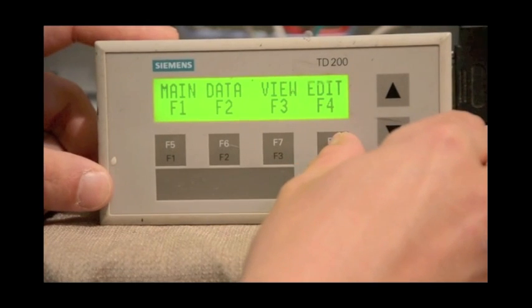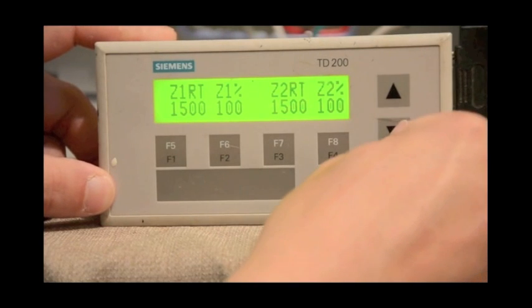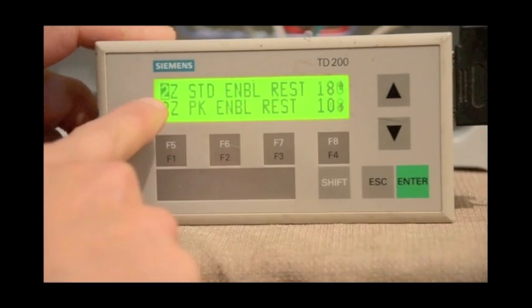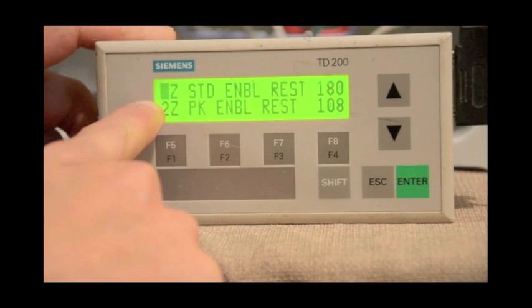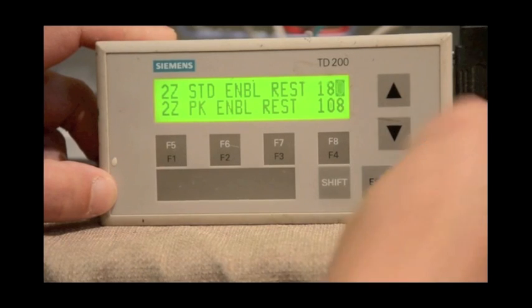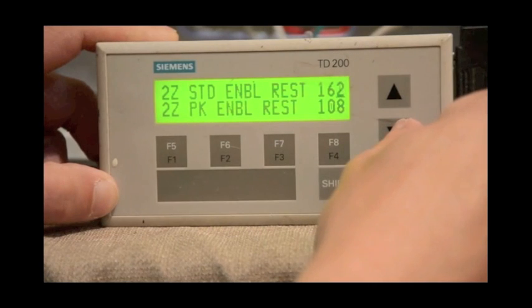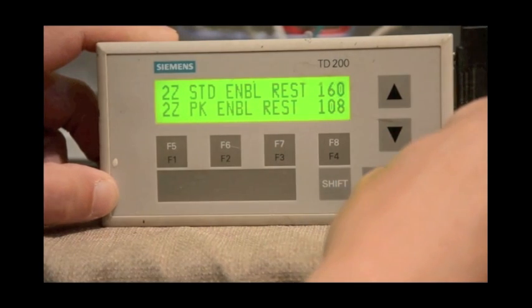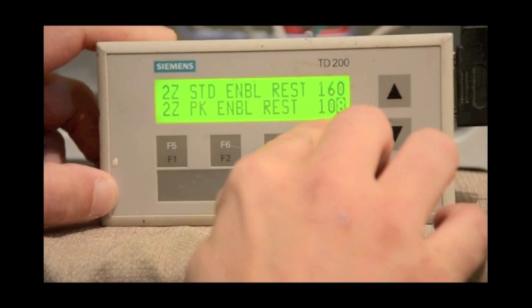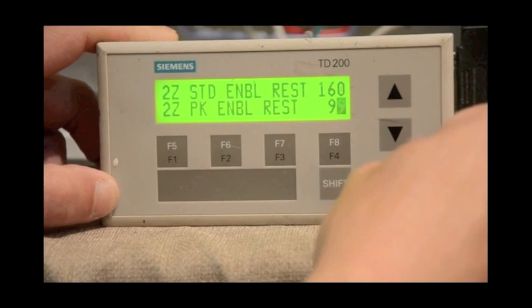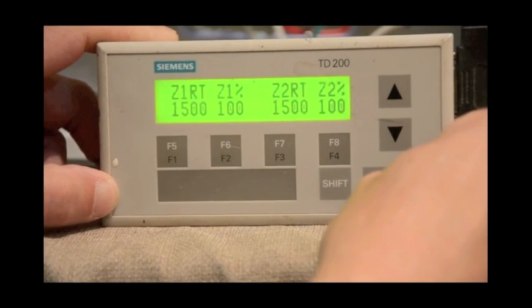Adjusting the rest times is also done using the F4 edit button. Once you've hit F4, use your down arrows to scroll down to the number of zones that you have in your system. In our case, we're playing with a 2 zone. Once the cursor is flashing on the correct line, press enter to move to the adjustable time. Using your down or up arrow key, adjust the rest time to your desired value. You can also press enter to move down to the peak rest time. These are independently adjustable. The same thing, go ahead and adjust your peak rest. Hit enter, which will take you back to the beginning of that F4 screen. You can come back to your zones to confirm that the data is now reset.